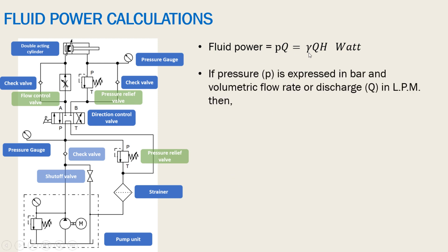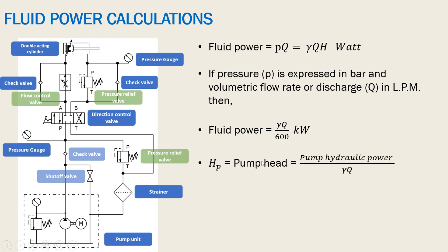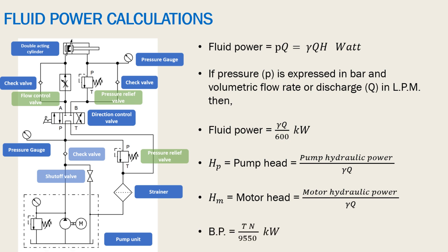If pressure is expressed in terms of bar and volumetric flow rate or discharge q in liters per minute, then we have to prove that fluid power is equal to p times q divided by 600, expressed in kilowatt. Then we will see how to find out the pump head, the motor head, and the brake power available at the shaft.